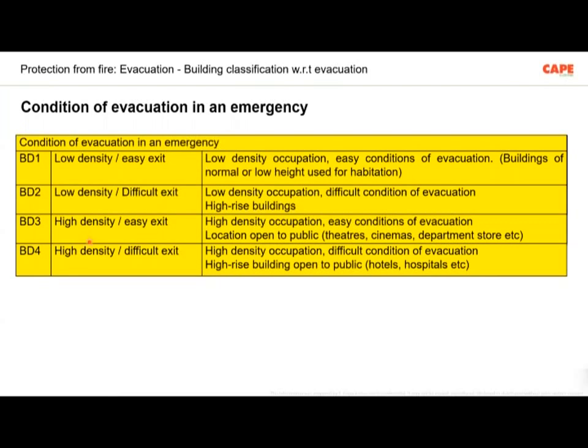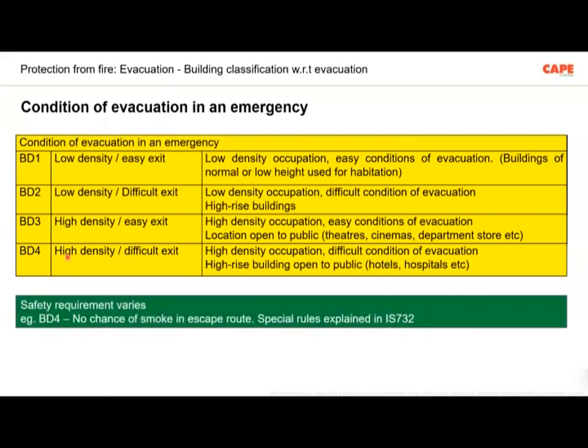The other categorizations also exist with respect to the content of the building, like explosives or flammable things, plus other classifications, for example a hospital where people are unable to move. But I am just focusing on the classification or condition of evacuation in case of an emergency. Four classifications are made. For each classification, such as BD2, BD3 and BD4, special requirements are there. Special wiring rules shall be adopted while designing and erecting the electrical installation. That is more important for us.